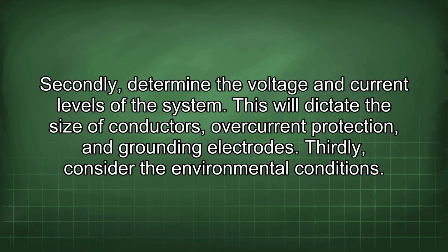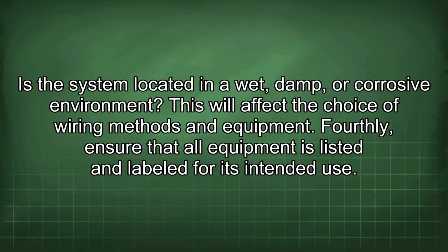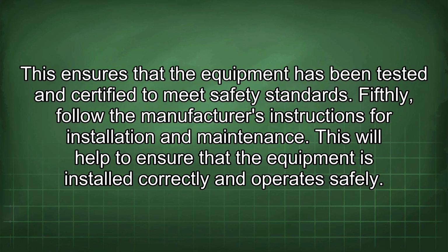Thirdly, consider the environmental conditions. Is the system located in a wet, damp, or corrosive environment? This will affect the choice of wiring methods and equipment. Fourthly, ensure that all equipment is listed and labeled for its intended use. This ensures that the equipment has been tested and certified to meet safety standards. Fifthly, follow the manufacturer's instructions for installation and maintenance. This will help to ensure that the equipment is installed correctly and operates safely.